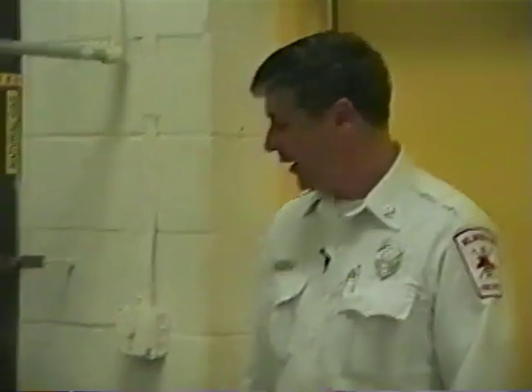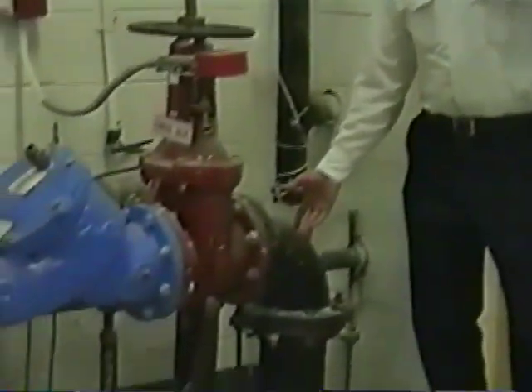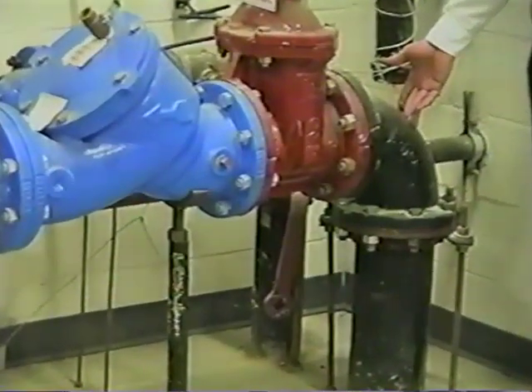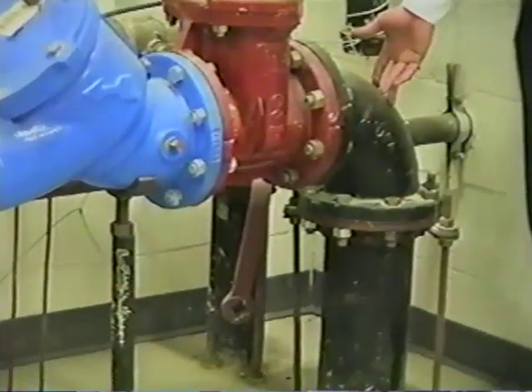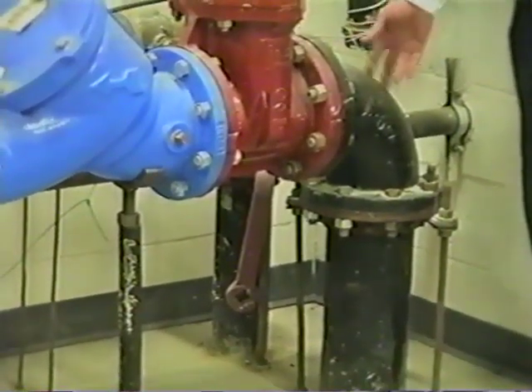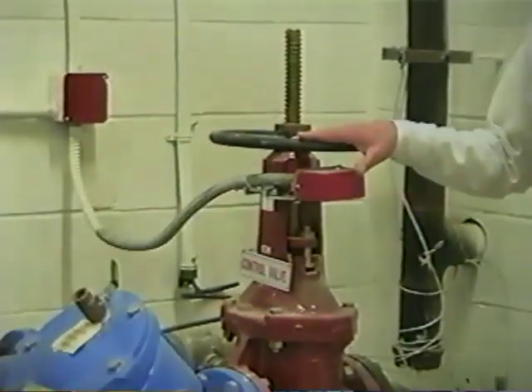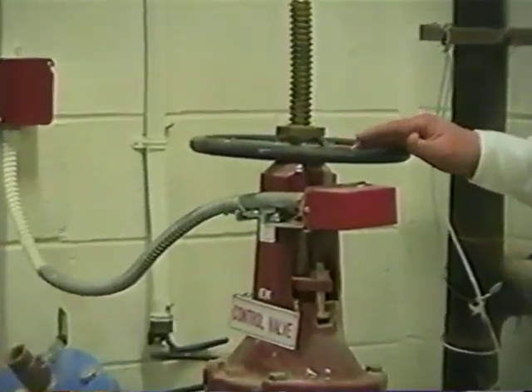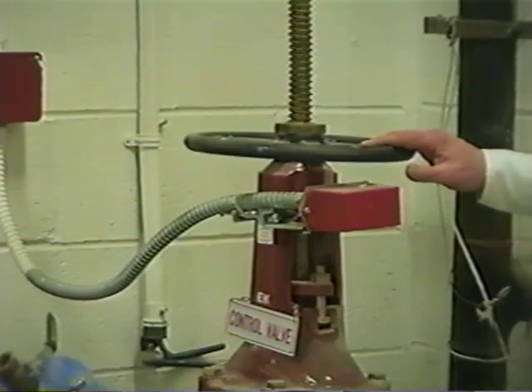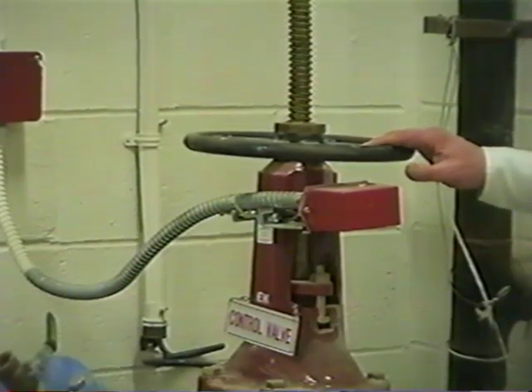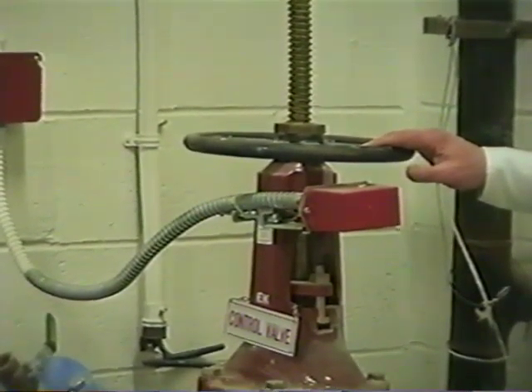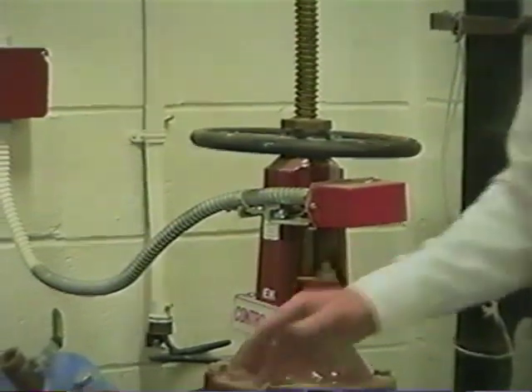Hello, we're in the sprinkler riser room at the Wilmington Public Safety Building. This sprinkler system is similar to many of the sprinkler systems throughout our community. This right here is where the water comes out of the street up through the floor that will supply water to the sprinkler system throughout the building. Up here, we have an OS&Y shutoff that the firefighters would use to shut down the water to the building in case we had to shut down the sprinklers after it put the fire out.